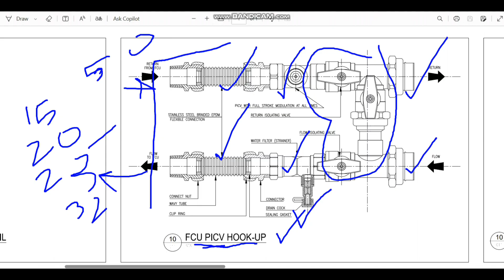This will not be available like a full package. Normally this is available for the lower sizes like a full package. You just connect this flexible connector with the FCU, and this connection you can make. All these parts will be available like a full package. But when it goes to the higher sizes like 50 mm or 40 mm, it will not be available like a full package. This will be available as individual parts. You have to procure the PICV, and you have to consider the isolation valve separately, then the strainer separately, and all this will be installed in a different way. It is not available like a full package. So when you go for the pricing as well as when you go for the order, you have to make sure that this package is only available for the lower sizes. Mostly in the Middle East this is the regular practice.